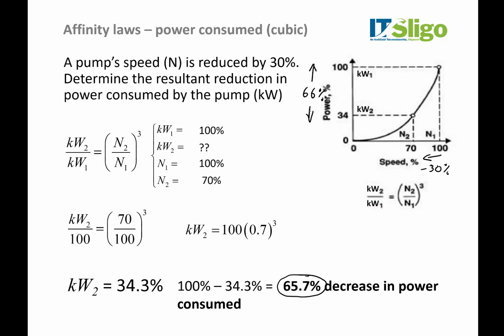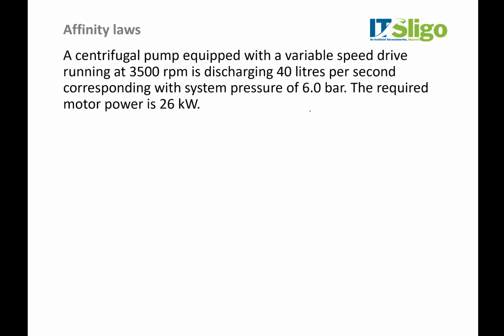So often it makes a lot of sense in industry to slow down pumps if it doesn't matter. You know, if you've got 2 days to fill a tank, pump slowly over a long period of time rather than turning on the pump for 3 hours at full blast. You would use a lot more power with the latter scenario, full blast, than you would with the slow, lower pump speed over a longer period of time. So just an example to work out.